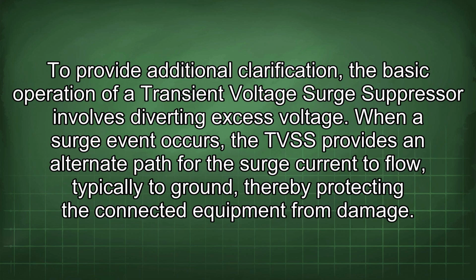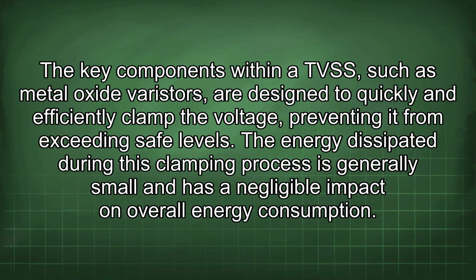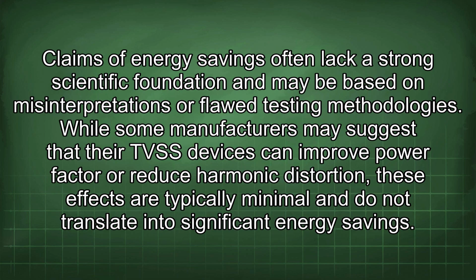To provide additional clarification, the basic operation of a transient voltage surge suppressor involves diverting excess voltage. When a surge event occurs, the TVSS provides an alternate path for the surge current to flow, typically to ground, thereby protecting the connected equipment from damage. The key components within a TVSS, such as metal oxide varistors, are designed to quickly and efficiently clamp the voltage, preventing it from exceeding safe levels. The energy dissipated during this clamping process is generally small and has a negligible impact on overall energy consumption. Claims of energy savings often lack a strong scientific foundation and may be based on misinterpretations or flawed testing methodologies.